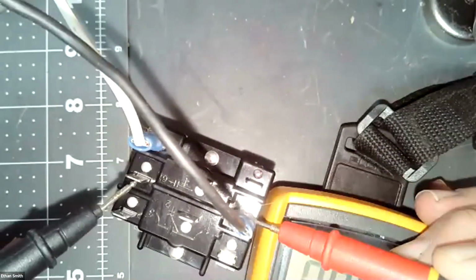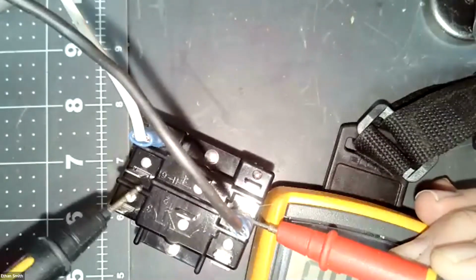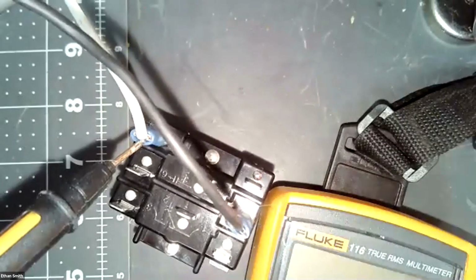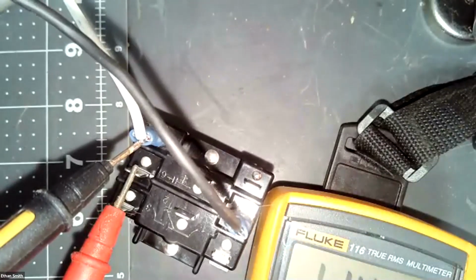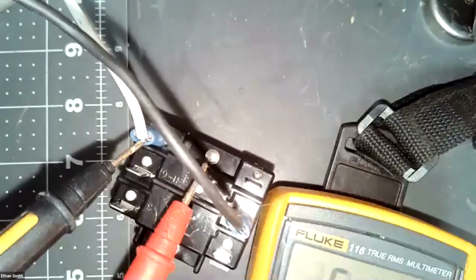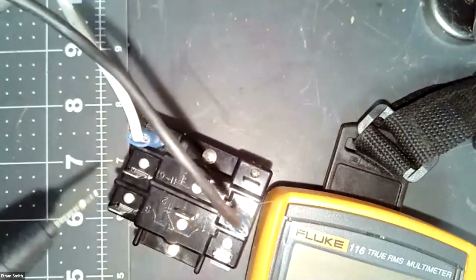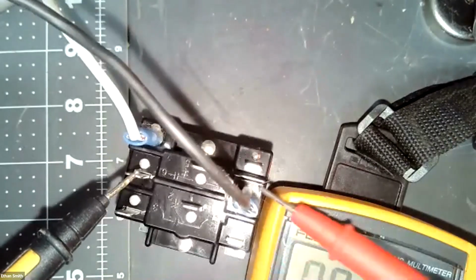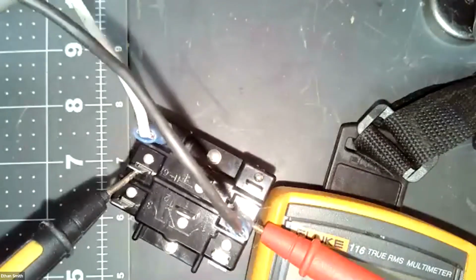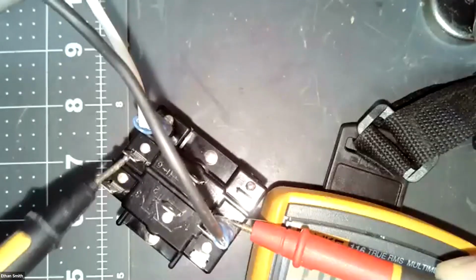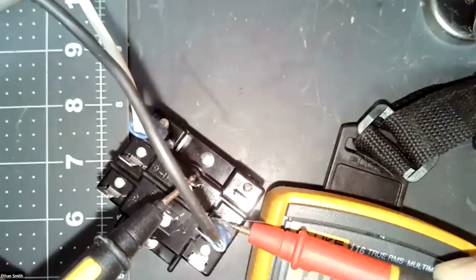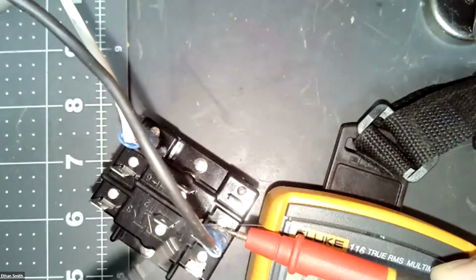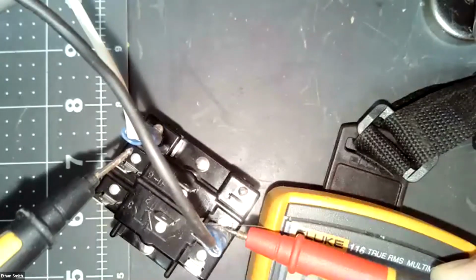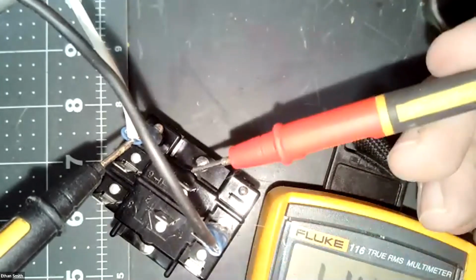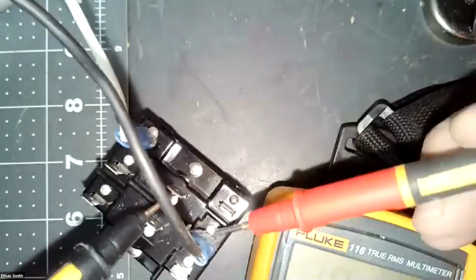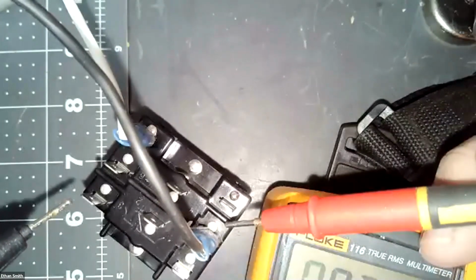But if I go to this one, which is normally open, now I don't have anything connected to this, so I'd have to go to a common. So if I go common, to that side, I got nothing. But here I've got voltage because I'm not connected. But if I go, come on, there to common, yep. But here I've got nothing, okay, because I'm not connected to anything on this side. So there I've got no voltage because it's closed. If I go to neutral, I've got 26 volts there. If I go to the other side of my switch, I also have 26 volts because we've got a continuous path here to here. Okay, that makes sense?